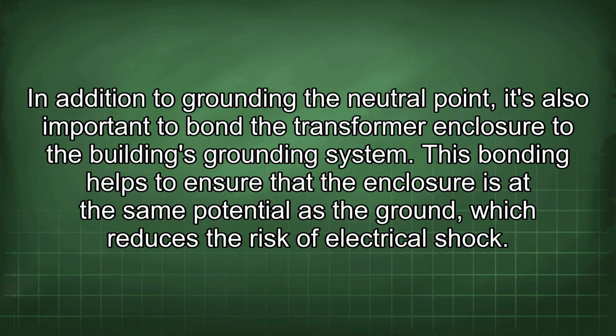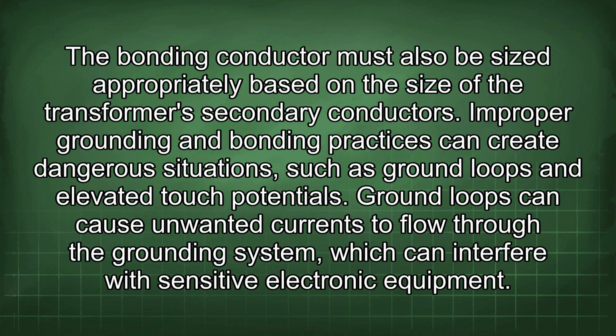In addition to grounding the neutral point, it's also important to bond the transformer enclosure to the building's grounding system. This bonding helps to ensure that the enclosure is at the same potential as the ground, which reduces the risk of electrical shock. The bonding conductor must also be sized appropriately based on the size of the transformer's secondary conductors.